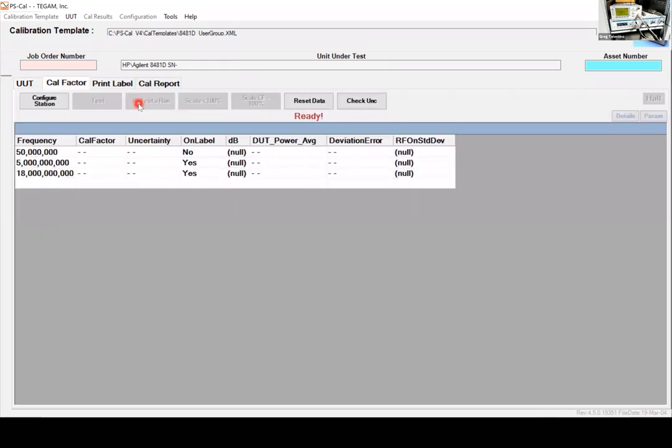So I've created this template prior to getting started on the webinar. We're going to go ahead and just go straight into Cal Factor. I deleted out most of the frequencies for purposes of this demo. I just want to show the process and how to get this calibration started. So you can see in the video, I have an E4418 Bravo and a TEGAM 1830A, along with a TEGAM 2505A. That's all the test equipment we'll need. The generator is sitting down below, so that's the equipment that we'll be using for this test.